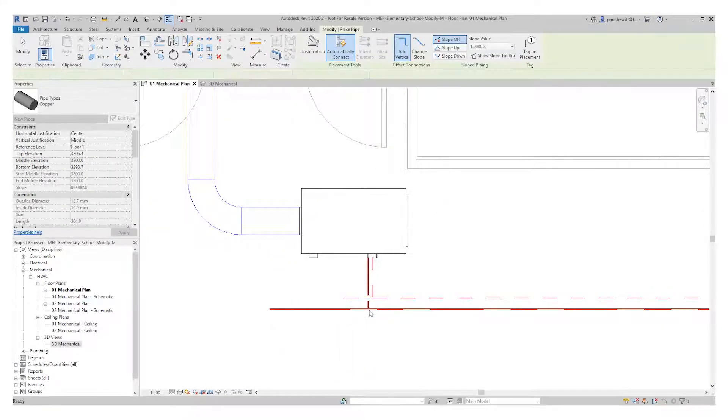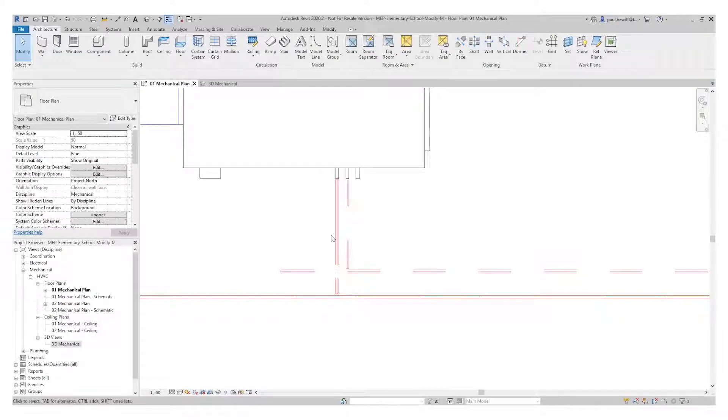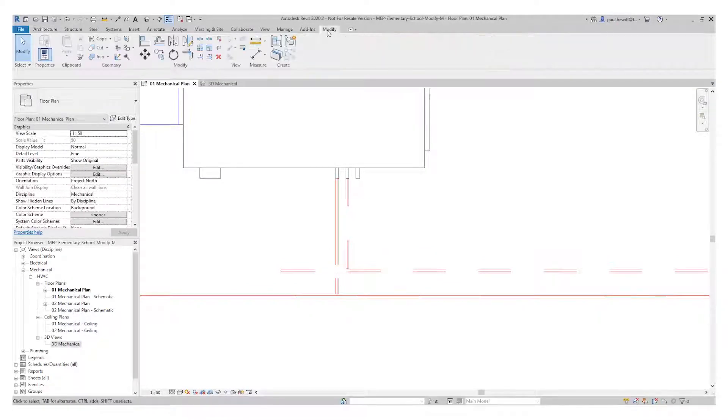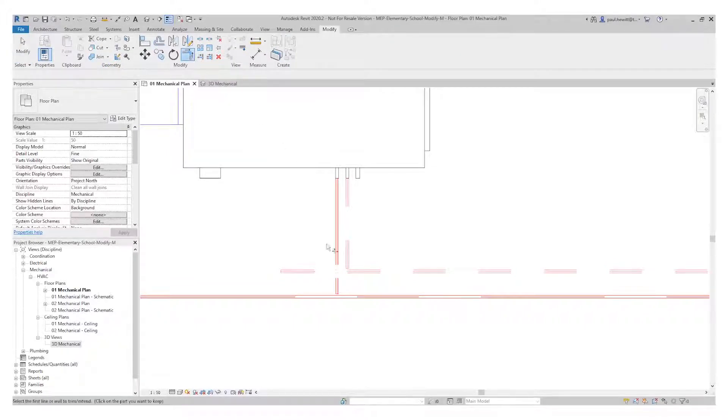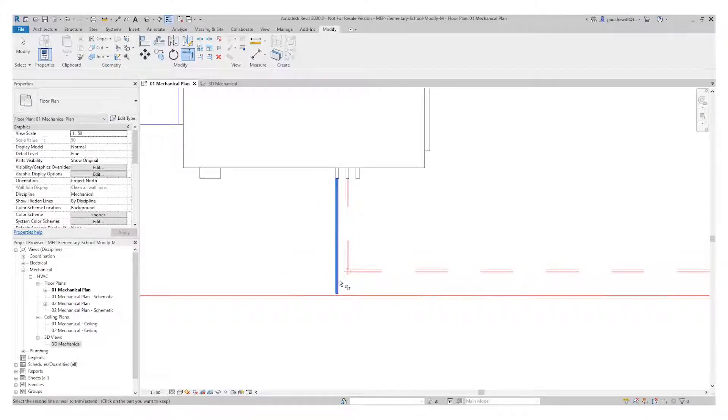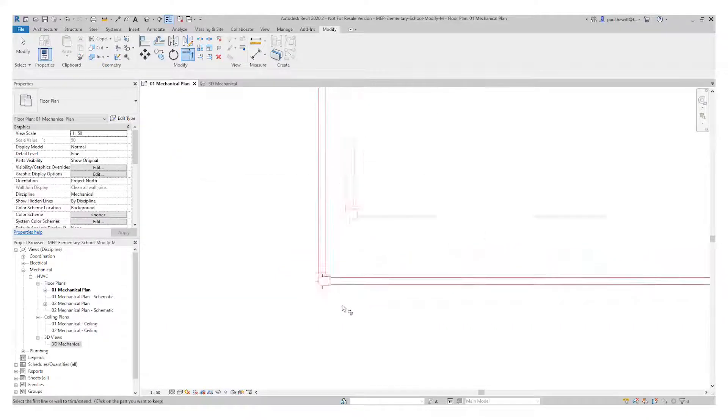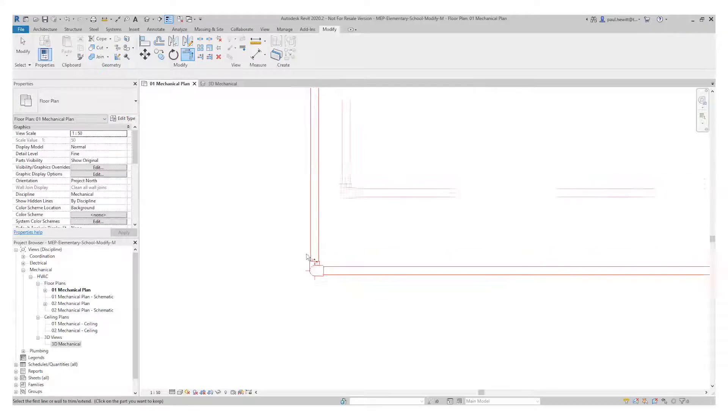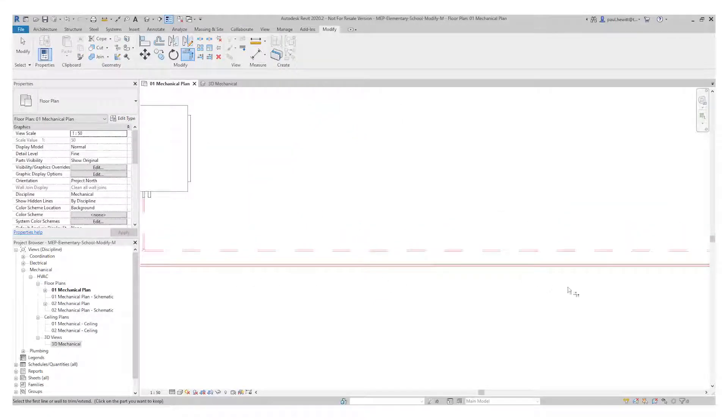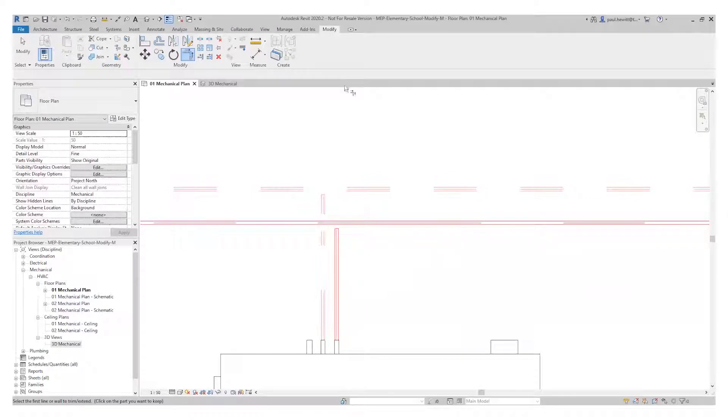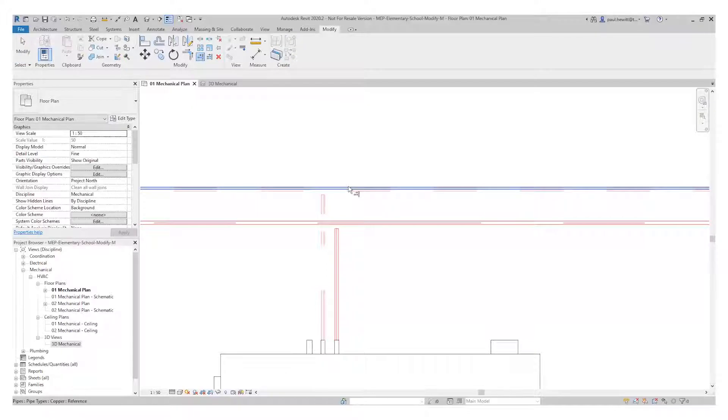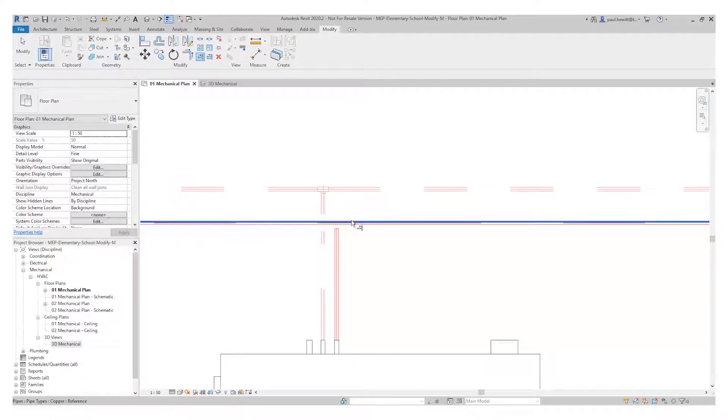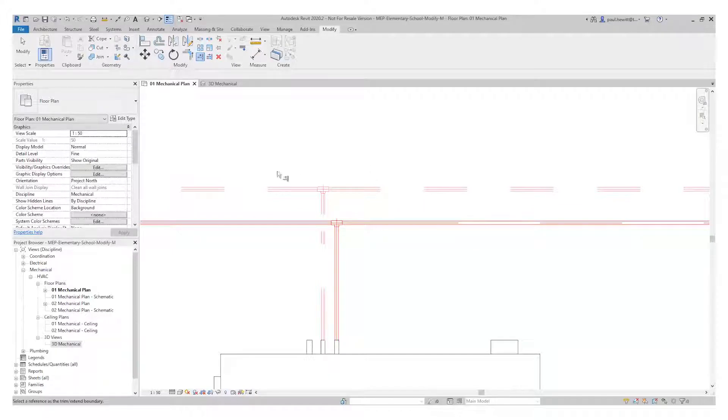So now I need to actually just tidy these up. You'll find that these aren't actually connected, they're just running next to each other. So in here, what I'm going to do, use the modify tool. I'm just going to use the trim and extend to corner. And I just select the two pieces of pipe that I want to keep, and it will actually add those components in there for my bends and so on. Now for the AHU unit further down, you'll see the pipes don't actually touch, so I'm going to use the trim and extend single object. So all I do now is just connect the bits I want to actually connect into the main pipework. And there you can see the connectors all set up for me.